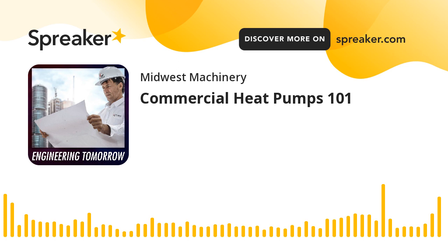In general, efficiency-wise, are they going to be about the same? Is heat pumps better? That's an ongoing question. Since it's difficult to rate a VRF unit because of the variance in refrigerant lines and how far it's going away and back, it's kind of hard to compare. But ASHRAE at their headquarters building, I don't know, about 7 or 8 years ago, when they were building their new building, installed VRF on one floor, and on an identical floor installed water source heat pumps with a geothermal well. And comparing geothermal to VRF, geothermal blew it out of the water in energy savings. I would imagine. Yeah, so geothermal compared to VRF, it's not even close.